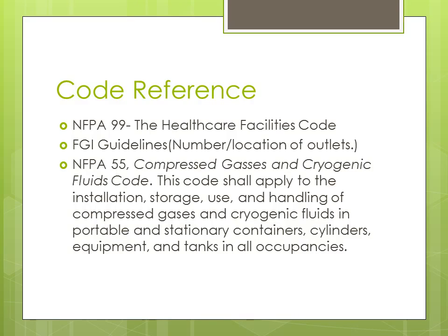NFPA 55, which is something we probably don't spend a lot of time on as healthcare facility leaders, but maybe we should spend more time on, really addresses bulk storage and compressed gas and cryogenic fluids code. It says this code shall apply to the installation, storage, and use and the handling of compressed gases and cryogenic fluids in portable and stationary containers, cylinders, equipment, and tanks in all occupancies.